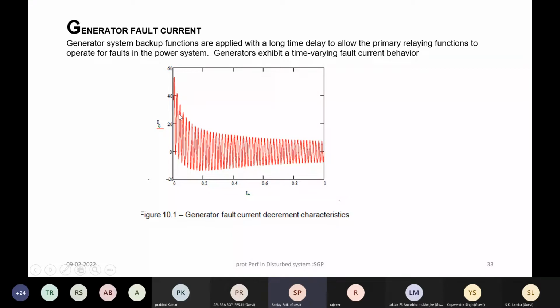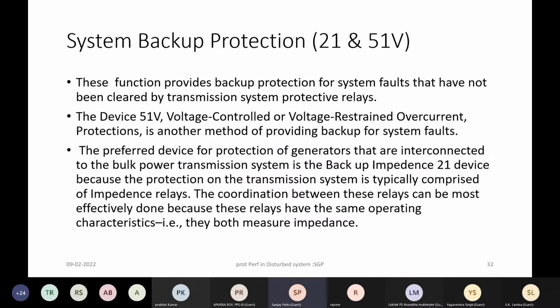So this is the sub-transient phase, this is the transient phase, and this is the steady state short circuit current. And this decremental nature of the fault current results in some of the generator backup protection schemes, especially the overcurrent protection scheme, not recognizing this as a fault current, because this current can sometimes approach very close to the actual load current. So one of the options is to go for a voltage restrained overcurrent relay, so that overcurrent accompanied by under voltage only is taken as a fault, or go for the distance protection, which we talked about here.